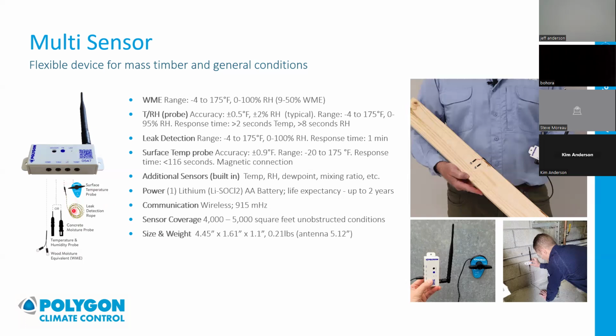And it's got a leak detection rope as well. So if we've got an area where we want to track the conditions in the air on a site, but there's also some concerns for whether water is going to get in, whether there's an opening in the building and rainwater is going to pour in, this rope can be plugged in, and if water touches it, it alarms. It's going to text people, email people, let everybody know that there's a potential issue in a certain area.